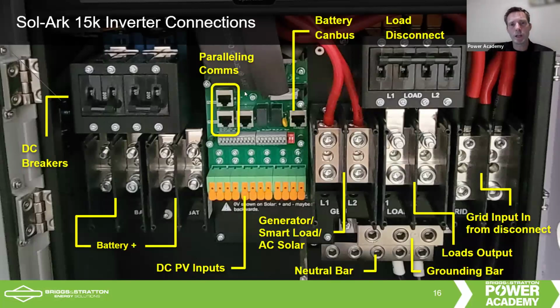The paralleling communications is all going to be on the communications board in the center, as are the DC PV inputs that are here. You can use the generator port as a smart load center. You could also, of course, use it as a generator port, or you could use it for AC coupled solar if you want to bring AC coupled solar. So you can use this as AC input or output on the inverter.